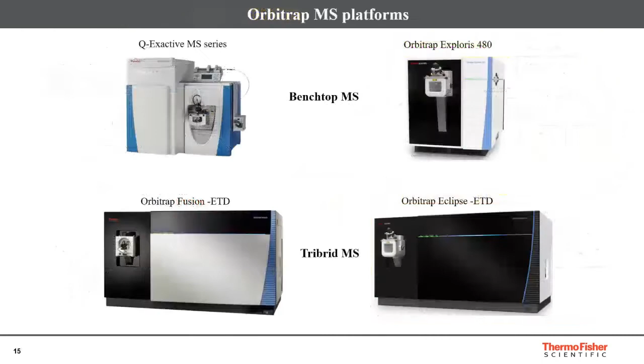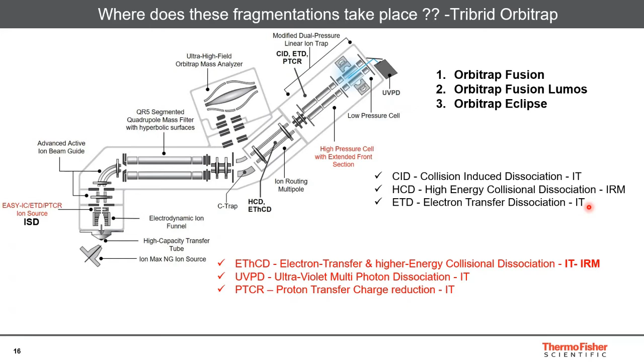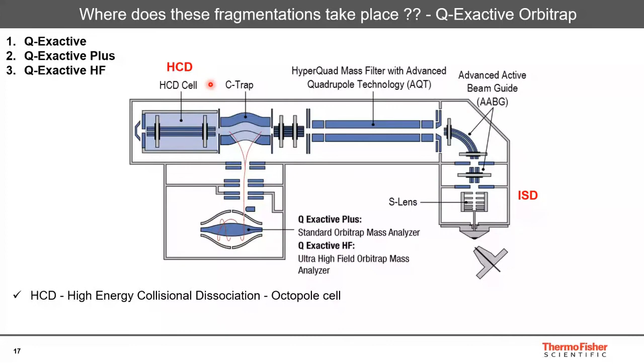This is an important slide wherein I am trying to highlight the different kinds of fragmentation techniques, fragmentation principles, that are possible within the tribrid Orbitrap instruments. It is possible to do CID, collision induced dissociation. It happens in the ion trap. And then we have HCD, high energy collision dissociation. It happens in the ion routing multipole. We do have ETD, electron transfer dissociation. It also happens in the ion trap. These multiple fragmentation techniques are really beneficial when we are trying to analyze analytically challenging molecules. A given molecule, you cannot simply fragment with one fragmentation principle, right? You may not get the required information, I mean the spectral fragmentation information. That is where multiple fragmentation techniques really help. And when it comes to the benchtop Orbitrap instrument, these two are possible: ISD, in-source dissociation, and HCD, high energy collision dissociation, right? So now let's go to the next slide.